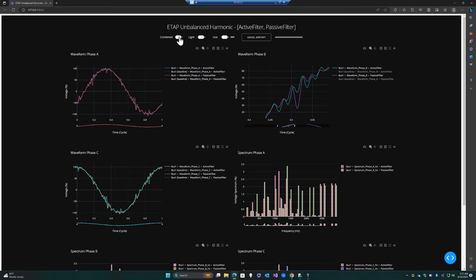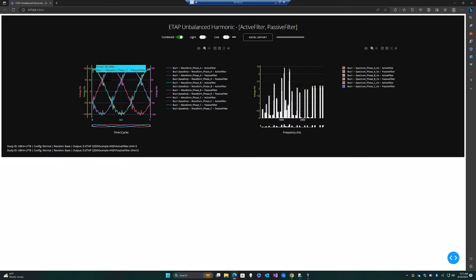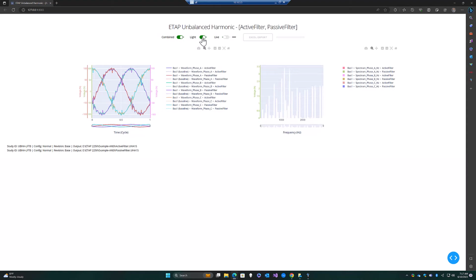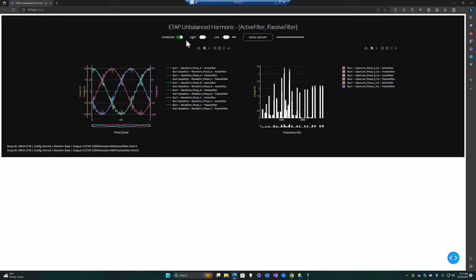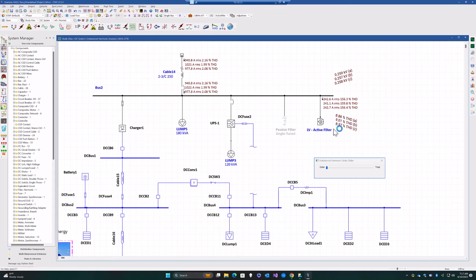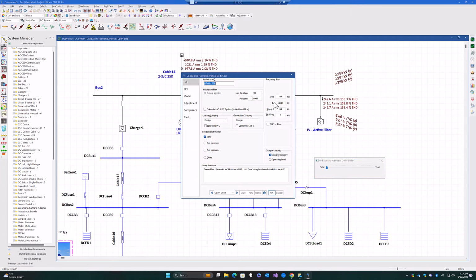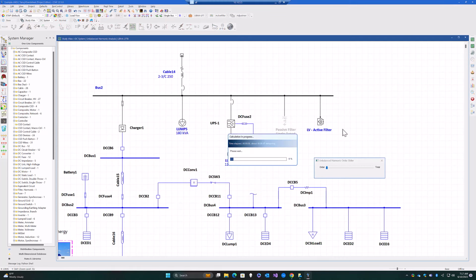And of course you can also combine these charts together, so you can see the ABC phases as well as the ABC spectrums together. And you also have, of course, the ability to switch between dark mode and light mode within these charts. All right, so that's the spectrum analyzer working with our unbalanced harmonics. And in order to see the time domain effect, we can go over to our study case, turn on the active filter in time, click OK, and rerun the analysis again.